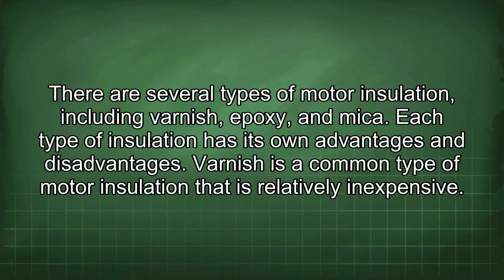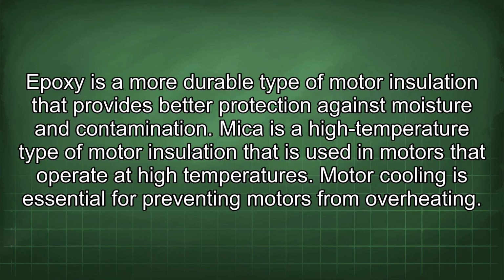There are several types of motor insulation, including varnish, epoxy, and mica. Each type of insulation has its own advantages and disadvantages. Varnish is a common type of motor insulation that is relatively inexpensive. Epoxy is a more durable type of motor insulation that provides better protection against moisture and contamination. Mica is a high-temperature type of motor insulation that is used in motors that operate at high temperatures.